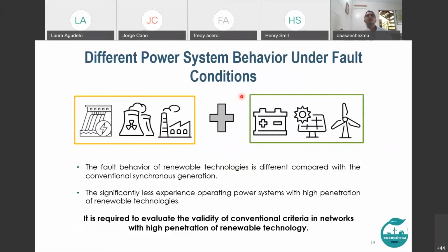The criteria is established according to system fault behavior, and we have to remember that renewable generation, due to its intermittence, needs a power electronics interface. This power electronics interface has a different fault behavior compared with a traditional synchronous machine. So what happens when we modify that fault behavior, including high amounts of renewable generation? Also, we have less experience operating this kind of resources. And this is why we need to evaluate what happened with conventional protection schemes technology. And this is our main purpose.